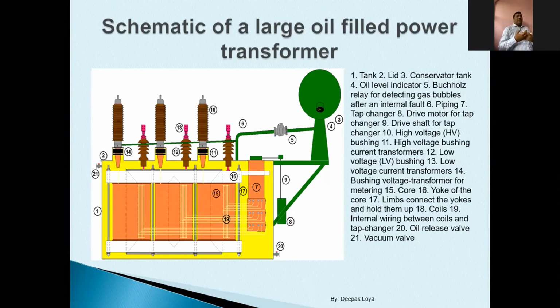So if I have to operate my transformer within these thermal limitations, we need this heat to be dissipated, or in other words, my transformer has to be cooled. And for cooling this transformer, we are using oil, a liquid, inside the transformer. Now, all this I am talking about because the third accessory or part in the transformer is the conservator. So what is the use of the conservator, or why is the conservator there?